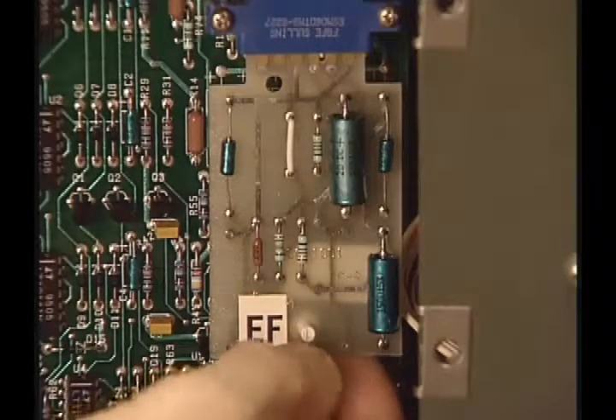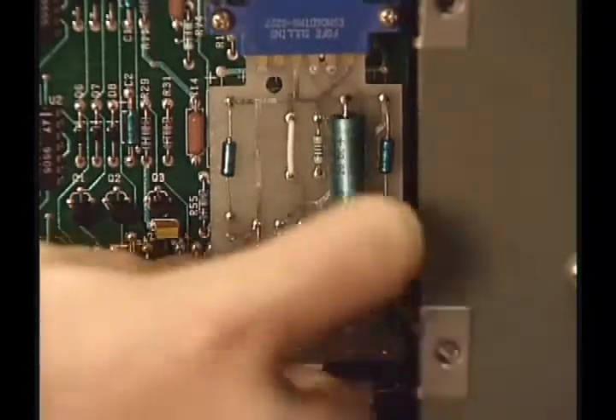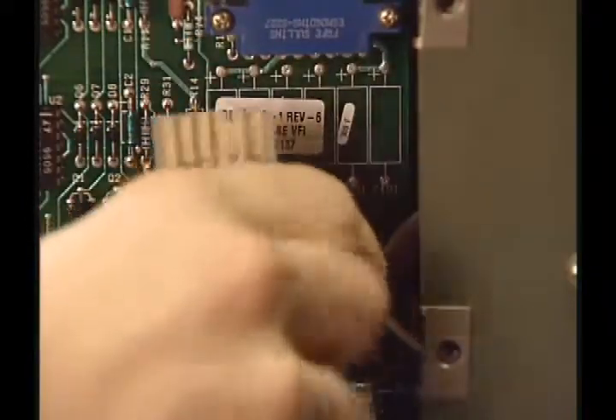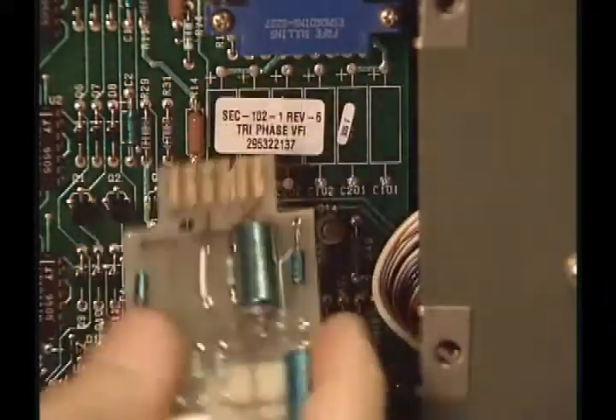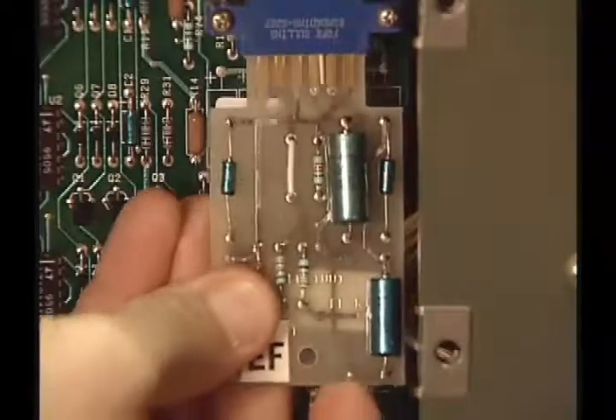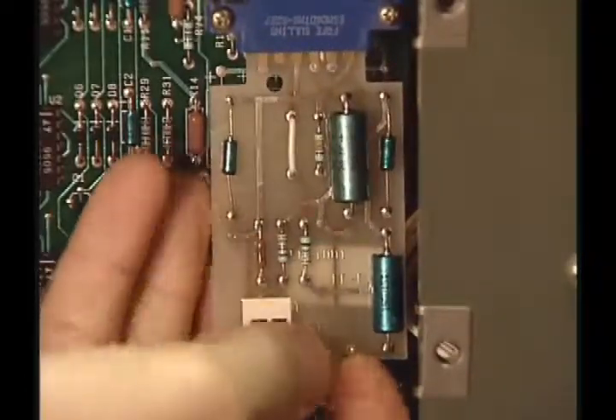Time delay curves are set by the TCC module. The control must have the module installed for proper operation. If it's missing while the switchgear is energized and a fault or overload occurs, the switchgear will trip in approximately 20 milliseconds. To replace the module, de-energize the switchgear if possible. Push down on the retainer clip and pull it free from the receptacle. Install the replacement module into the receptacle and snap it onto the support post.